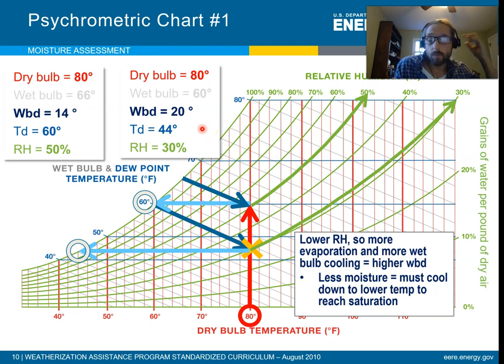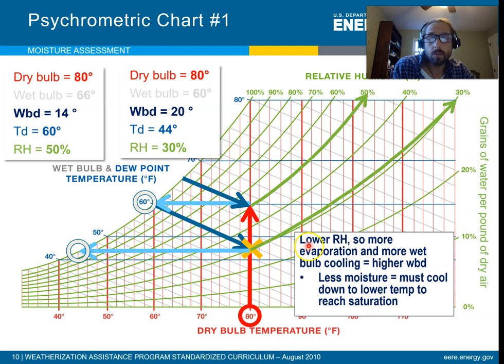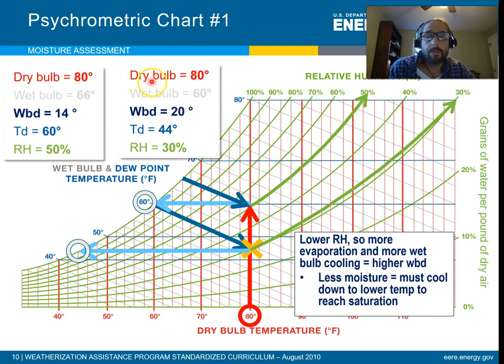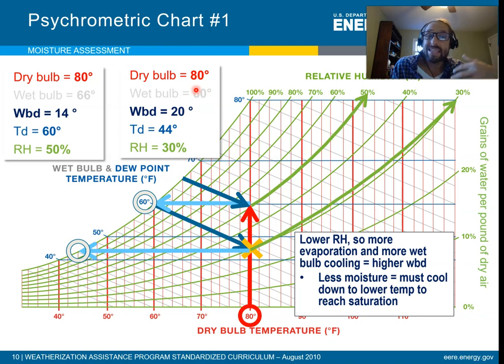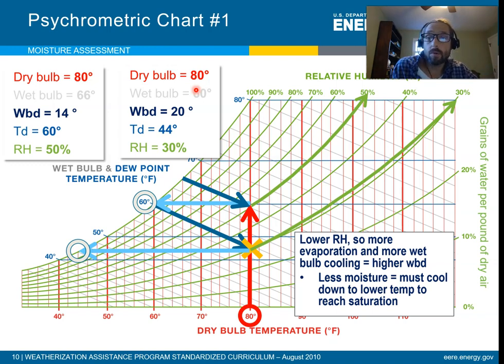A couple of lessons here. Number one, you can find any of the other variables as long as you have two of them. The other important thing to point out is that as you lower the relative humidity — the dry bulb stayed the same — because there's lower humidity in the air, there's less moisture, which means it's easier to evaporate. So you're going to get more evaporation on the wet bulb, which means more cooling, which means the wet bulb is going to drop and your wet bulb depression is going to go up.